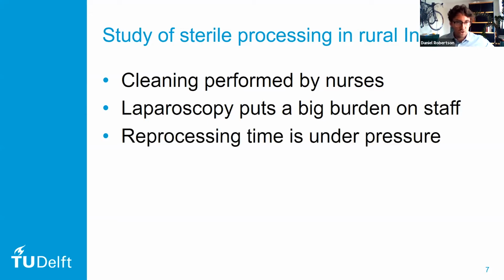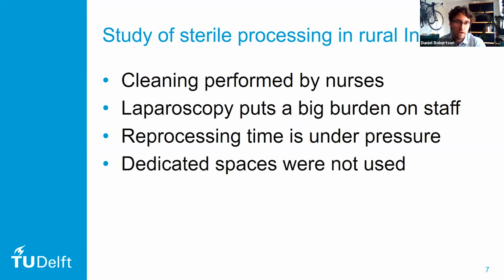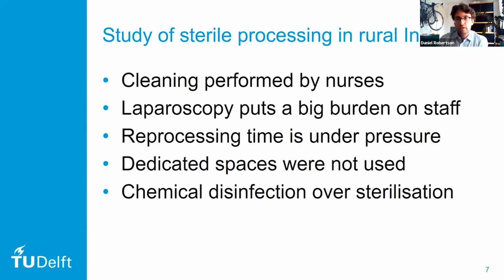And this means, because the nurses have to do all of the tasks between one surgery and the next, that they have very little time to properly reprocess all of the instruments. Now, because there was quite limited time, the instruments were not reprocessed in spaces that were dedicated for it. So a lot of the times, the instruments were moved outside of the operating room to a sink. And even in hospitals where there were dedicated sterile processing departments, they were not moved there, just as a measure to save time. The other thing is that for a lot of these hospitals, the laparoscopic instruments are very expensive.